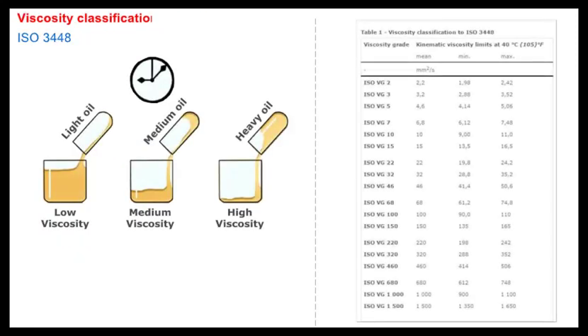ISO has defined a series of standard ranges for viscosity as defined in the table shown here. An ISO VG, viscosity grade, is defined by a midpoint with a possible deviation of 10%. For example, ISO VG100 denotes an oil that has a kinematic viscosity of 100 cSt, plus or minus 10% at 40 degrees Celsius. In other words, the viscosity is in the range 90 cSt to 110 cSt.